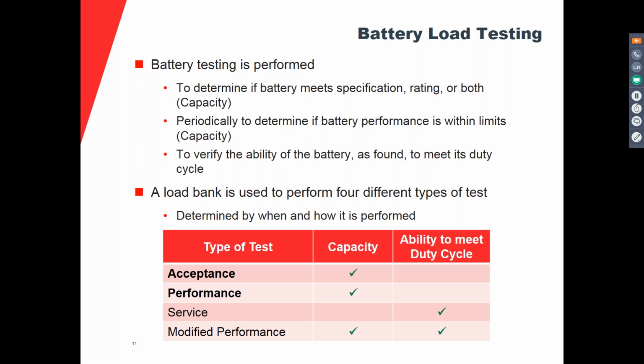You will do the test to determine if the battery meets the specification or the rating or both. Basically, you are measuring the capacity of the battery, and this is usually when the battery is new, when you are accepting it, when you are installing it for the first time. From that point on, you can do the test periodically to determine if the battery is performing within the limits, if it is capable of supporting the load, or to determine if the capacity is deteriorating or not. Another reason you can perform the test is that you might not be interested in the total capacity of the battery. You just want to know if the battery is capable of supplying the load for the time that you need the load to be supplied. That is another reason you perform the test.